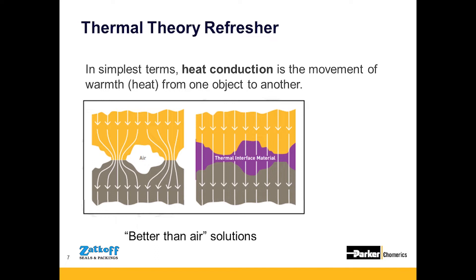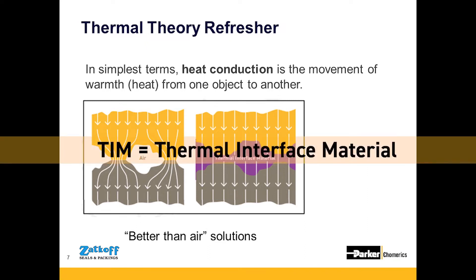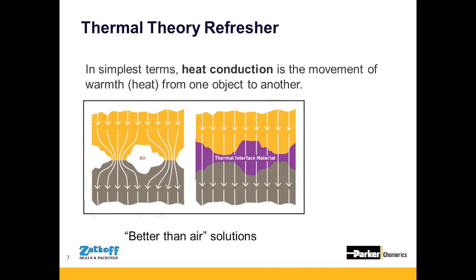Thermal theory refresher: thermal interface materials are meant to serve at the interface between a heat-generating component and a cold plate or cooling feature. They are better than air solutions because air is a good insulator. Throughout this presentation, we will refer to thermal interface materials as TIMs. TIMs use conduction to pull heat away, relying on contact between components to remove interstitial air gaps. Densely packed ceramic particles within silicone binders give TIMs excellent durability and thermal conductivity while ensuring electrical insulation.